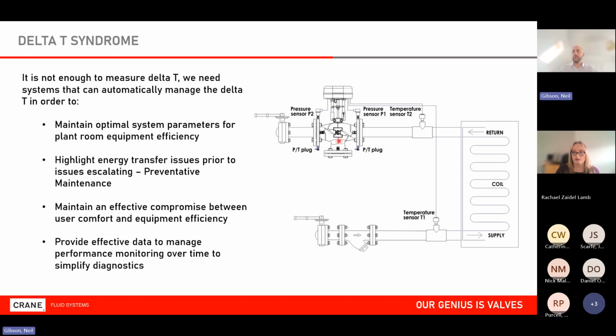So now, not only can I use these registers to monitor the values, if I set a limit, and we'll get onto this in more detail in a moment, i.e. I set T2 to 12 degrees Celsius, let's assume it's a chilled system, I can set it and the valve will automatically control itself to ensure that the return temperature is always 12. So it won't compromise on the delta T if the valve is being driven open to generate what it thinks is more power. In reality, it's just wasting energy. So I can set that limit. I can set a limit based on delta T. I can set limits based on power, because all of that information is now built in. And going back to my point at the beginning, the logic is built within the field device itself.